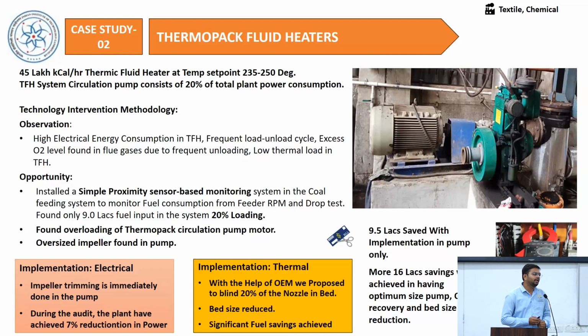After that, we recommended the industry reduce the number of nozzles. They blind some nozzles and reduce their firing bed, so that the thermic fluid output is reduced from 45 lakh kilocalories to about 30 lakh kilocalories. Because the industry is planning expansion in the future, we kept that in mind. We suggested cutting the bed according to the requirement, and we resized and redesigned the bed. They also achieved almost 20% fuel reduction with this implementation.